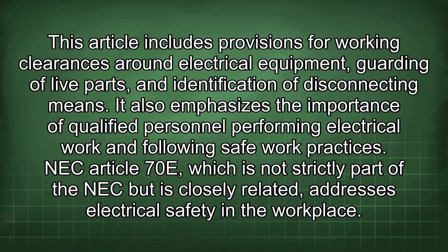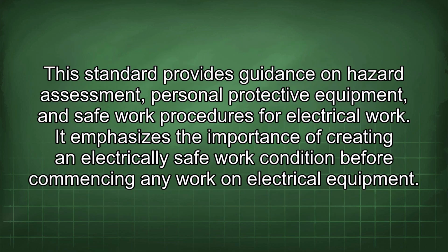This article includes provisions for working clearances around electrical equipment, guarding of live parts, and identification of disconnecting means. It also emphasizes the importance of qualified personnel performing electrical work and following safe work practices. NFPA 70E, which is not strictly part of the NEC but is closely related, addresses electrical safety in the workplace. This standard provides guidance on hazard assessment, personal protective equipment, and safe work procedures for electrical work. It emphasizes the importance of creating an electrically safe work condition before commencing any work on electrical equipment.